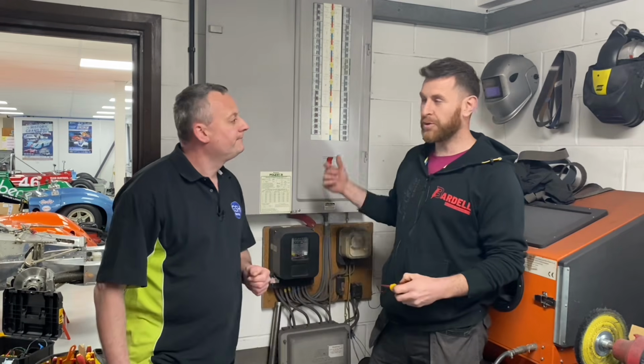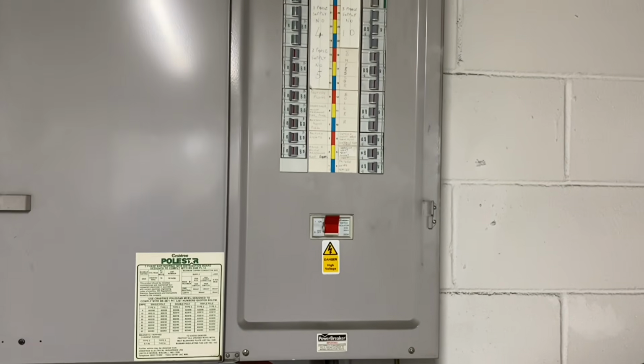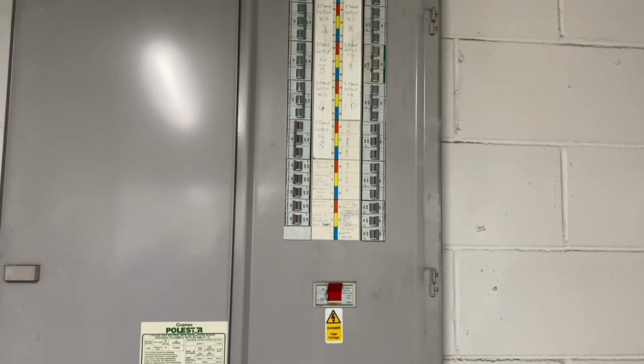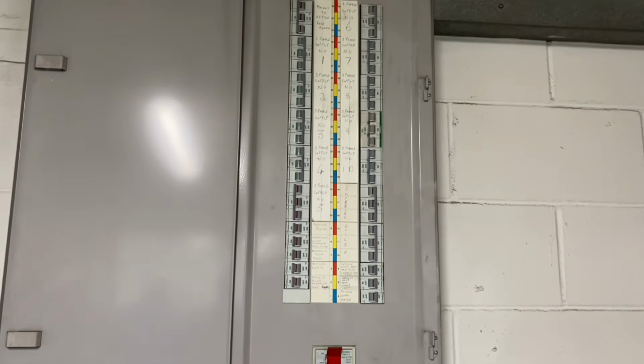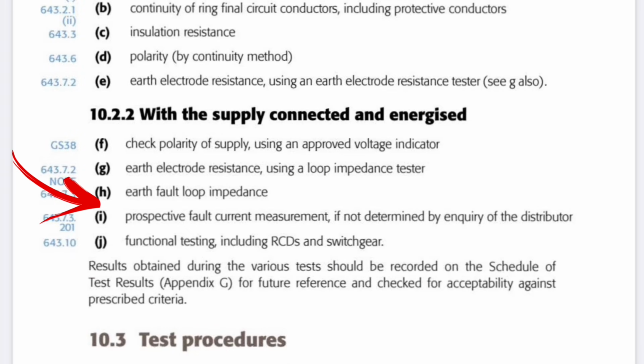It's a real treat for the channel. We're back out with big sexy Matt O'Dell, and we're going to try today to go through some of those tests that are going to be required for AM2 and AM2S. And which one are you going to pick out first that we're going to have a go at? So in particular, we've got the three-phase board. Yeah. So we can do the earth fault loop impedance, yes, the external earth fault loop impedance, and then the PFC. Yeah, so they're really crucial for AM2S, AM2, and well, if AM2E, if you're doing the experience route as well. And we're going to make sure that we don't miss out a part, especially now we've got a three-phase board, because often at colleges they're working on single-phase installations, aren't they?